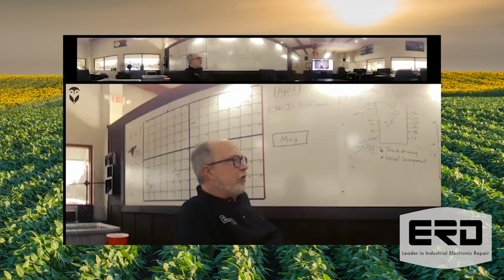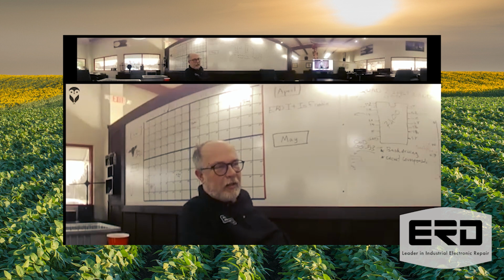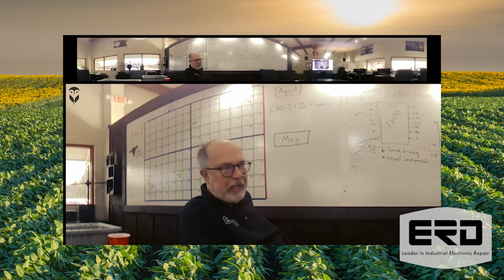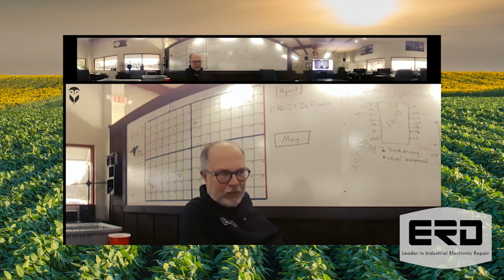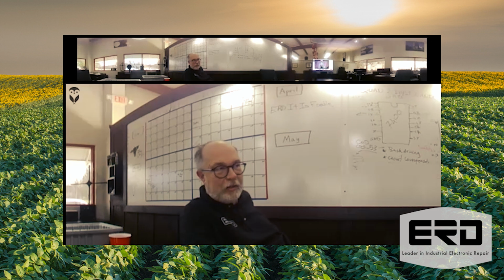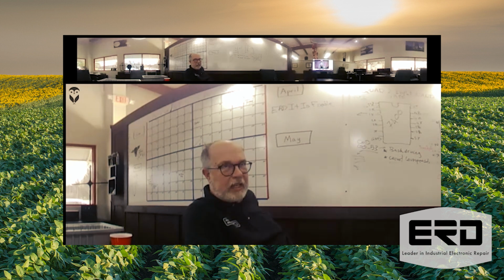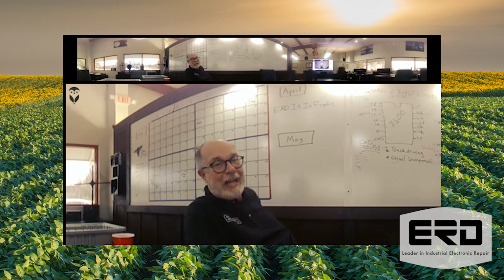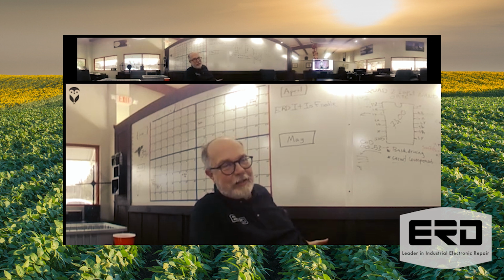Yeah, okay, the main issue we see is basically age: the electronics has been doing its job day in, day out, year after year, and it needs to be rebuilt and cleaned up. Our average age of equipment we get in is between 10 and 20 years, and it's never been worked on. That speaks volumes to the earlier quality of some of this equipment. If you have a 20-year-old piece of equipment and now you're getting it serviced, hey, that's not bad. You're not going to buy a new one, but you can get it serviced.